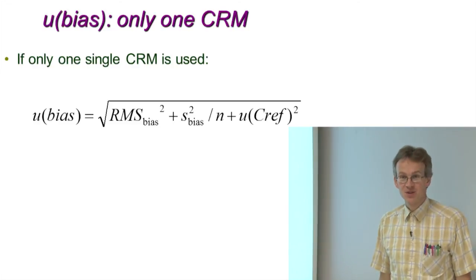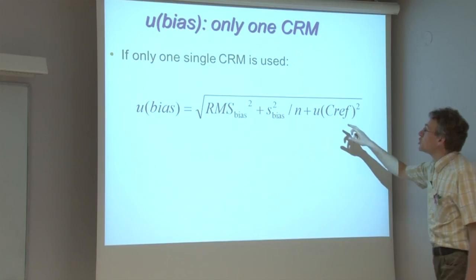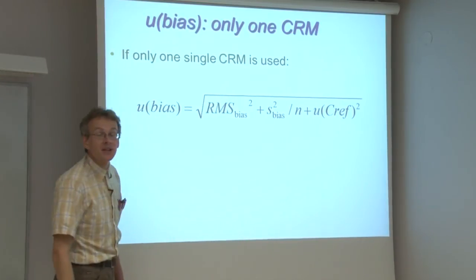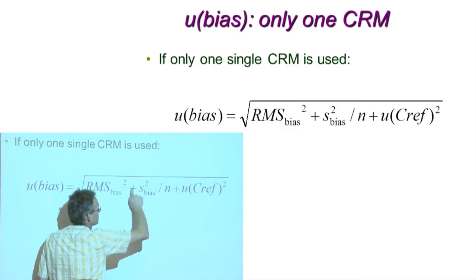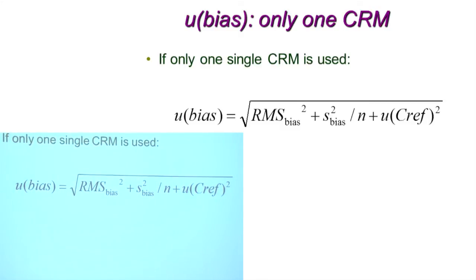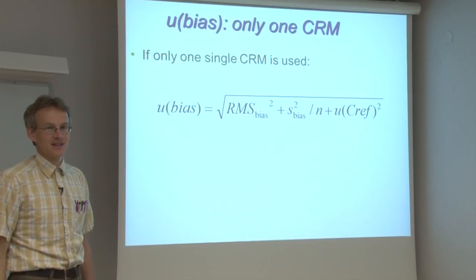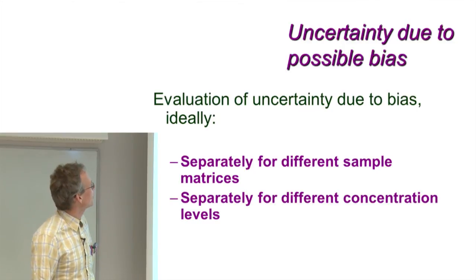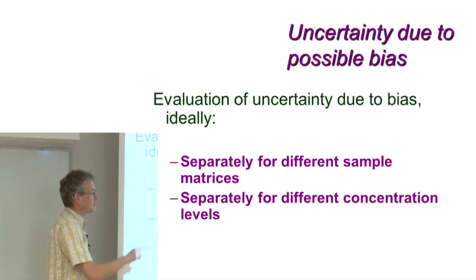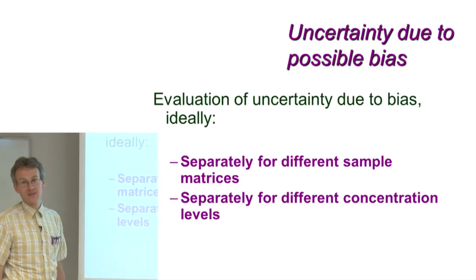If unfortunately you have only one single certified reference material for bias estimation, but you can do several bias determinations with it, then the U_bias formula changes slightly. The RMS_bias squared and UC_ref squared remain the same, but in addition you must bring in an extra term: the standard deviation of the bias values obtained divided by the square root of how many bias determinations were carried out. Such an additional term is required when only one single certified reference material is used. As with the random component U_RW, the bias should preferably be estimated separately for different matrices, and also separately for different concentration levels if very different concentrations are used.